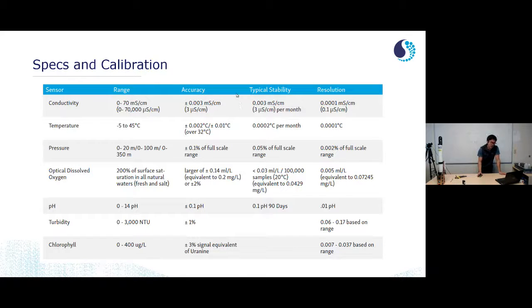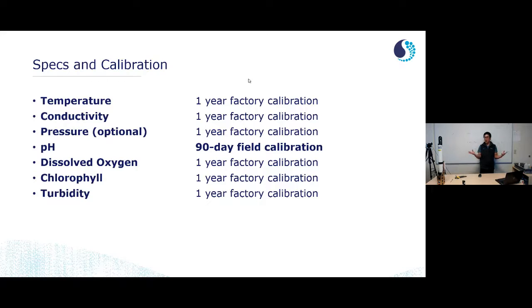So speaking of the pH sensor, all of the sensors, except for the pH sensor, have a 1-year factory calibration. This is pretty standard for Seabird CTDs, where we recommend recalibrating your instrument every year in our world-class calibration baths to really maintain the optimal spec of these sensors.